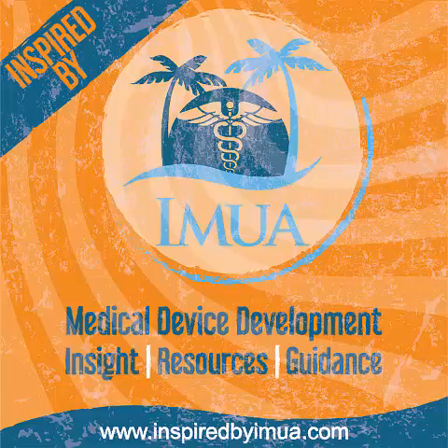In medical device, and really in many products, food requires this as well, there's something called shelf life. Shelf life is a generic term, and what we mean by that is how long does my widget, my product, stay good, if you will, just to use simple language. And good is usually meeting your specifications for whatever that is. So we use the environmental chambers to do something called accelerated aging, which allows us, using temperature, like a catalyst, to accelerate chemical reactions to create a real-time equivalent.